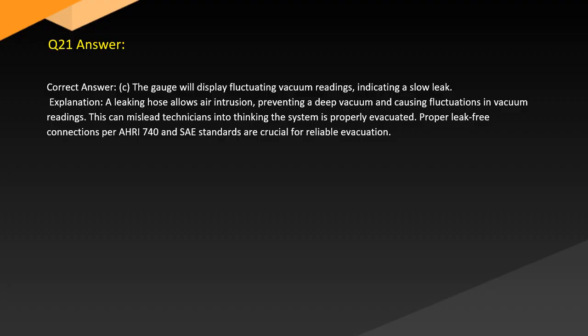Answer. Correct answer: C. The gauge will display fluctuating vacuum readings indicating a slow leak. Explanation. A leaking hose allows air intrusion, preventing a deep vacuum and causing fluctuations in vacuum readings. This can mislead technicians into thinking the system is properly evacuated. Proper leak-free connections per AHRI 740 and SAE standards are crucial for reliable evacuation.